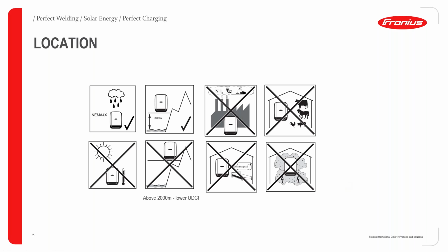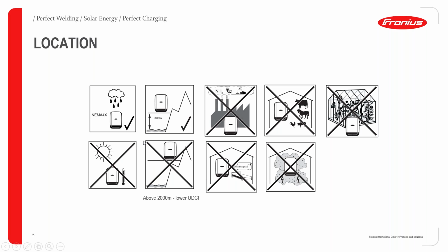Great. So in terms of installation location, sorry, let me go one step back. We have do's and don'ts in terms of the location for installation. Like I said earlier, it can be installed outside and can withstand rain. But it is better to install it under shaded conditions, or as we normally do in most cases, under the modules themselves. That is for outdoor or ground-mounted installations, thereby preventing it from direct impact from the sun. Because if that happens, you're going to have increased temperature, which might affect the ambient temperature, and of course might affect the output of the inverter in terms of derating.